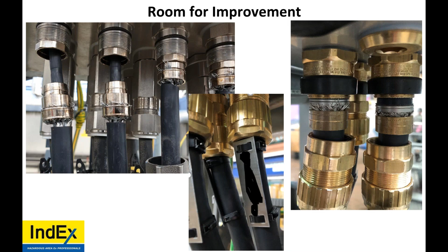What's the significance of the armoring? If it is not properly terminated, there is the chance for ignition. Also, if there's a cut in the cable, the point is that the fault current will hopefully travel through that armor into the gland, through the device, and go to the equipotential bonding—the path of least resistance—not through a human or through a piece of equipment, and hopefully not cause an ignition.